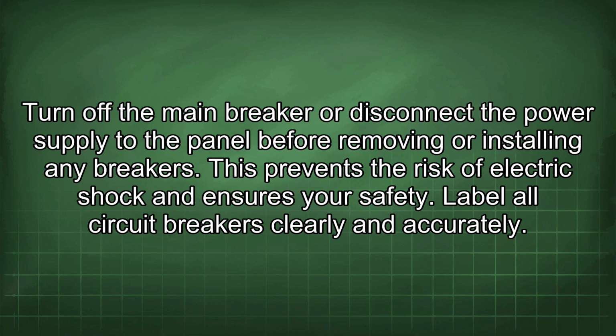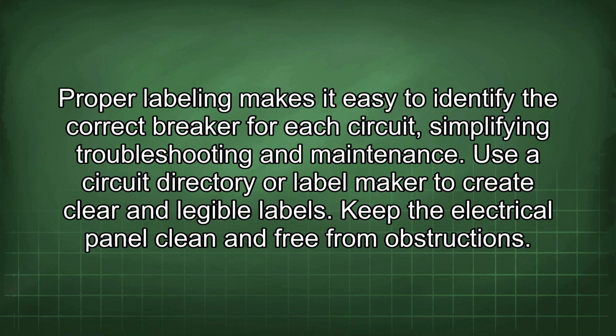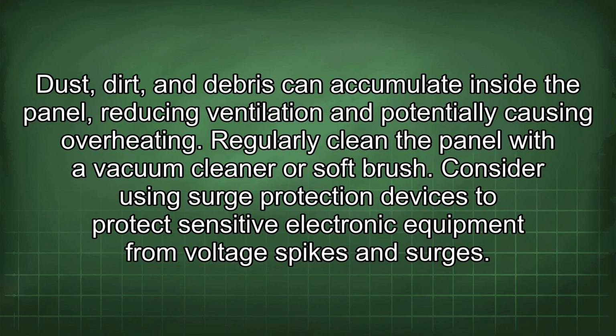Label all circuit breakers clearly and accurately. Proper labeling makes it easy to identify the correct breaker for each circuit, simplifying troubleshooting and maintenance. Use a circuit directory or label maker to create clear and legible labels. Keep the electrical panel clean and free from obstructions. Dust, dirt, and debris can accumulate inside the panel, reducing ventilation and potentially causing overheating. Regularly clean the panel with a vacuum cleaner or soft brush.